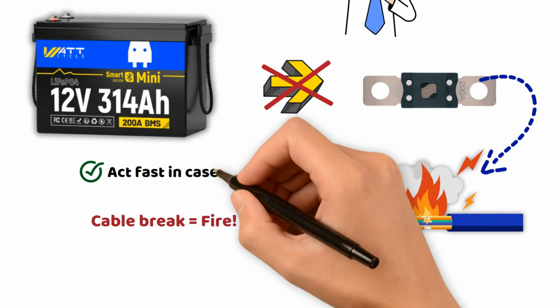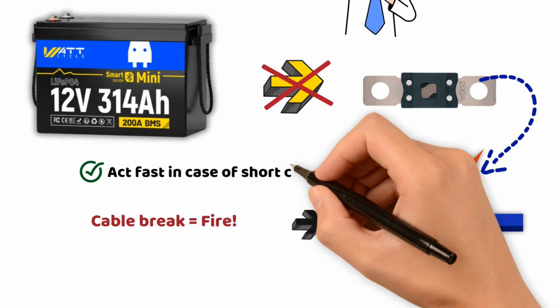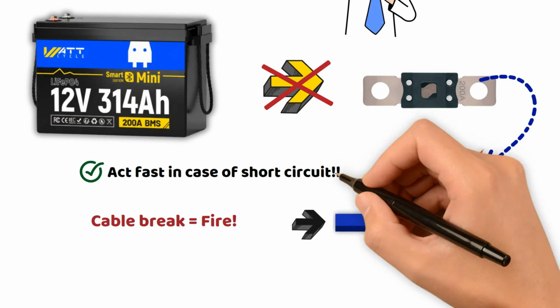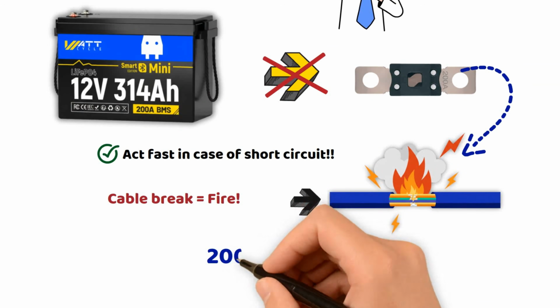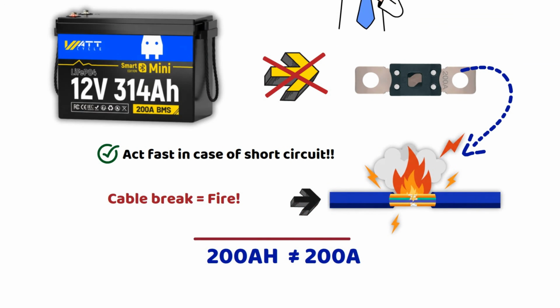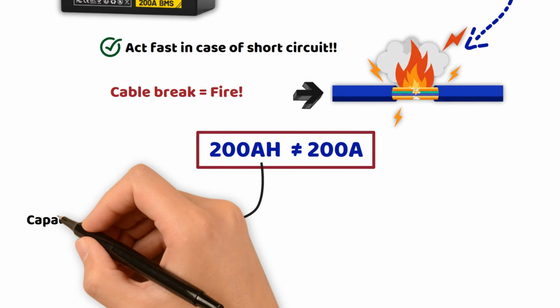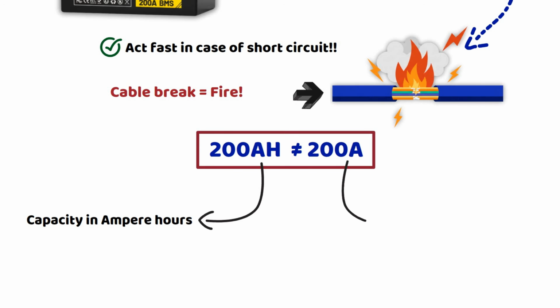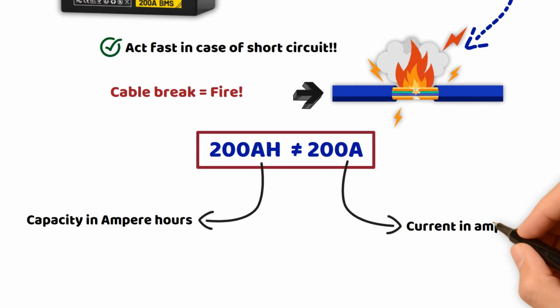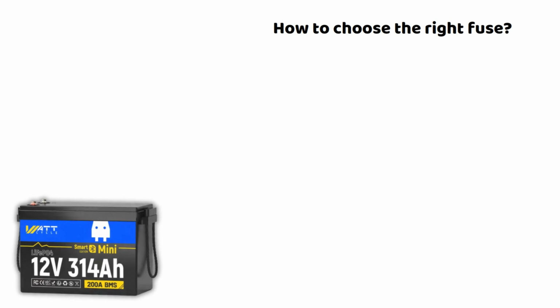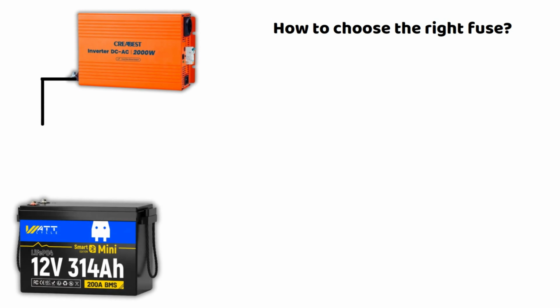The fuse must be able to stop this current spike thanks to its breaking capacity to prevent the wires from melting. This is why you should never choose the size of a fuse based on the battery's capacity, but only according to the maximum current that the inverter will consume. To illustrate our demonstration, we'll use two devices that I particularly like: the WattCycle 12-volt, 314 amp-hour mini battery, and the Creabest 2000-watt inverter at 12 volts.